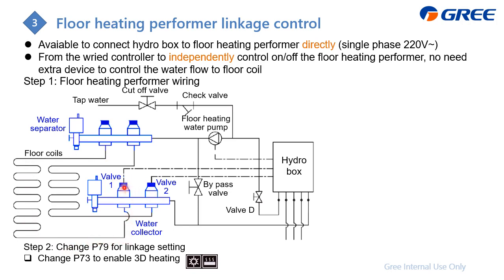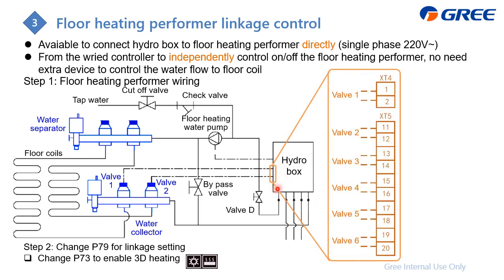We can connect this valve 1 and 2 to the hydro box directly, which means from here we can control this valve directly. How to control it is from the wire controller, which means from the wire controller we can control this valve directly and don't need any other device. And here there is a wiring which offers you up to 6 valves. We can control up to 6 valves.